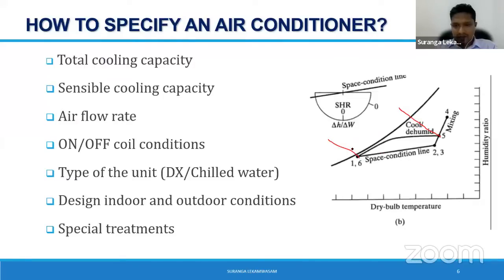This is your off coil condition. This enthalpy gives you the cooling capacity, or the cooling coil size, right? When you dump this off coil air, chilled air, into your room, room heat will bring this point up to this point, right? You can see if your room sensible heat is higher, this line becomes more and more flat, right? Because there is less latent heat.